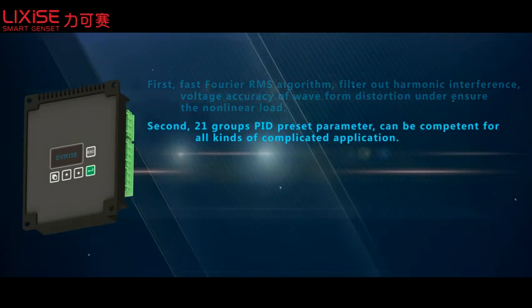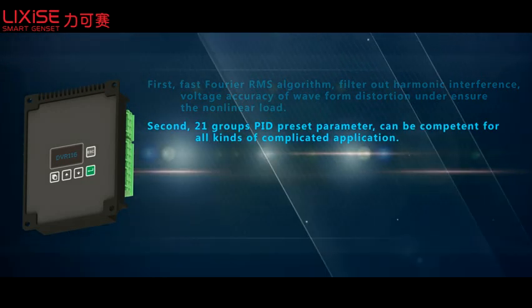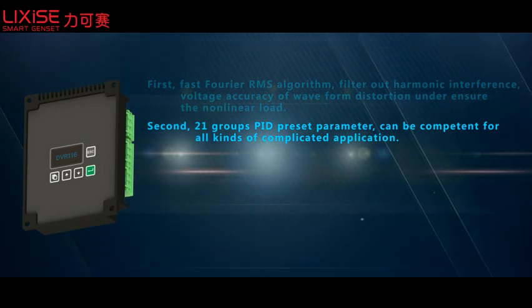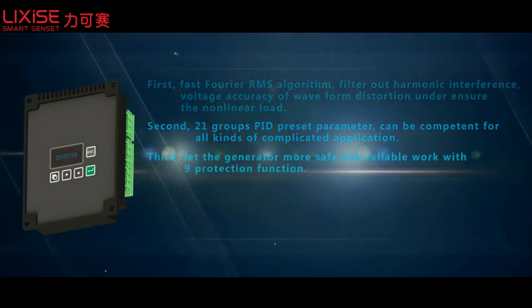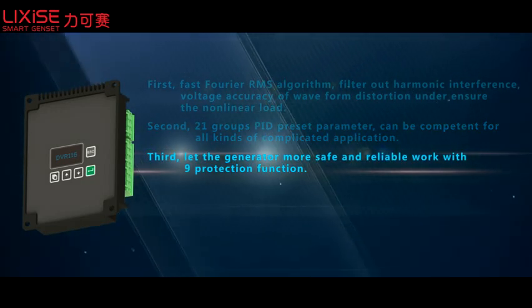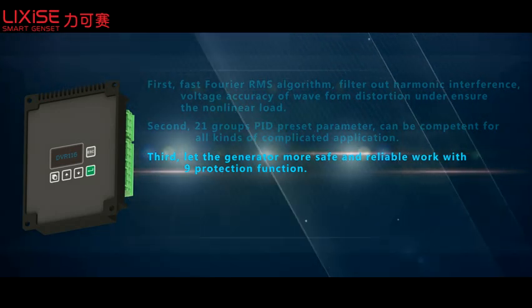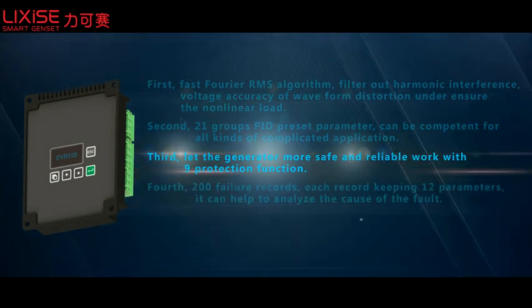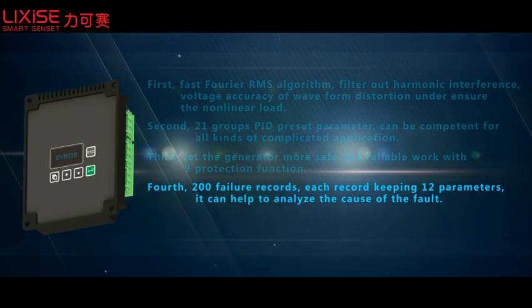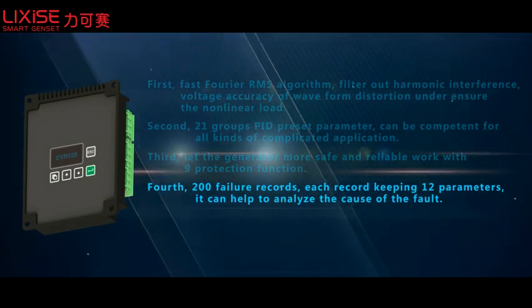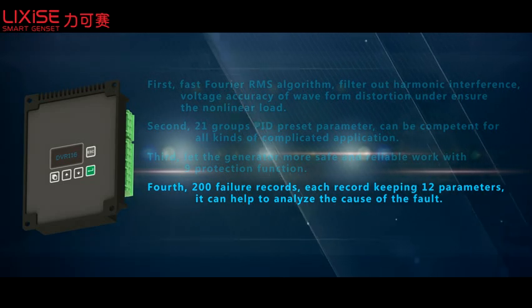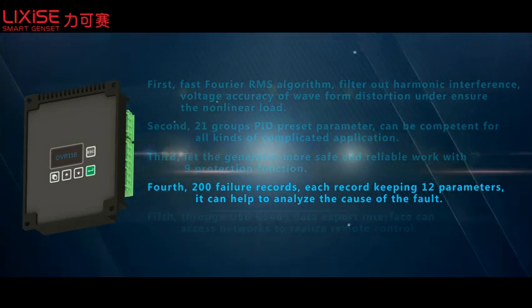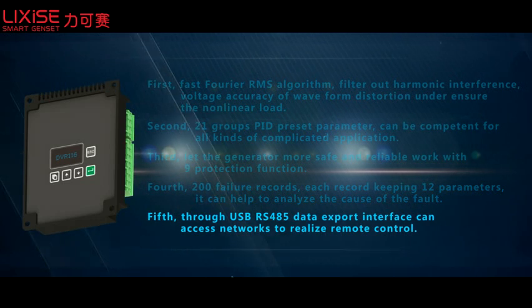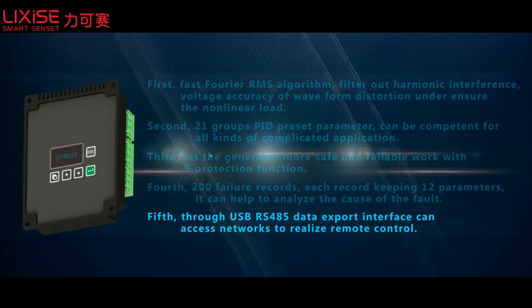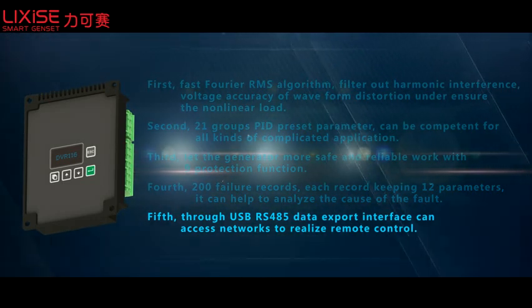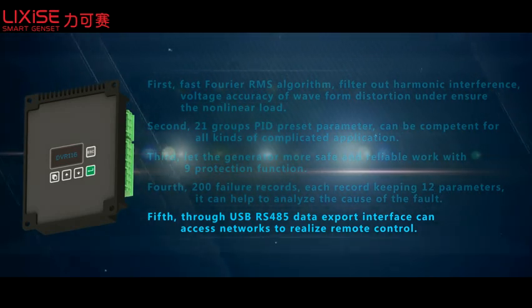Second, 21 groups of PID preset parameters can be competent for all kinds of complicated applications. Third, let the generator be more safe and reliable. Work with 9 protection functions. Fourth, 200 failure records, each record keeping 12 parameters. It can help to analyze the cause of the fault. Fifth, through USB RS-485 data export interface, it can access networks to realize remote control.